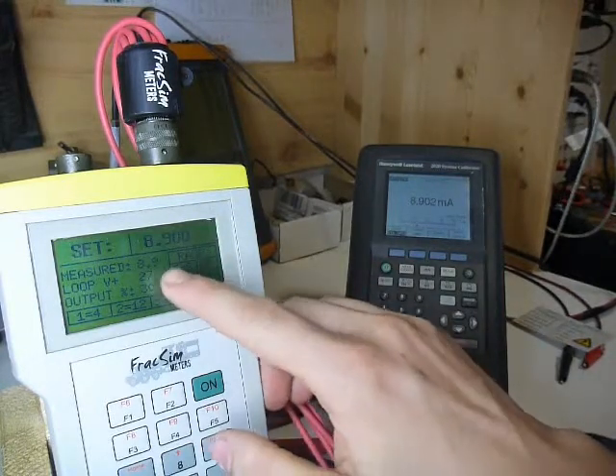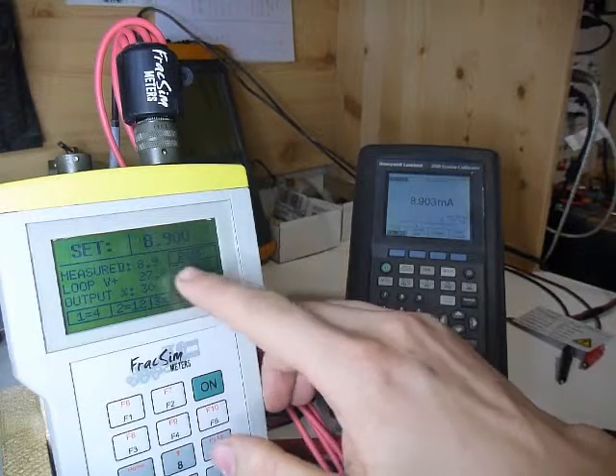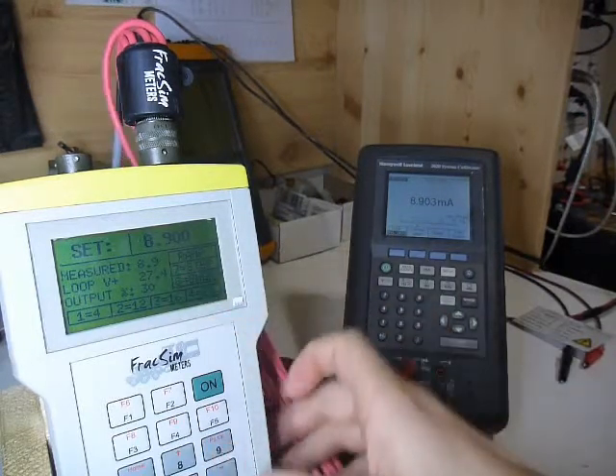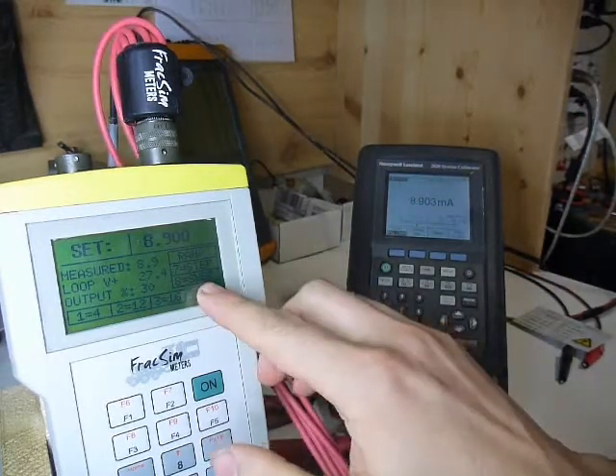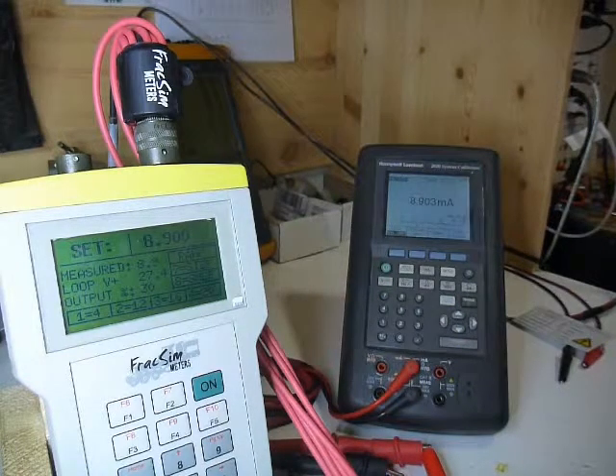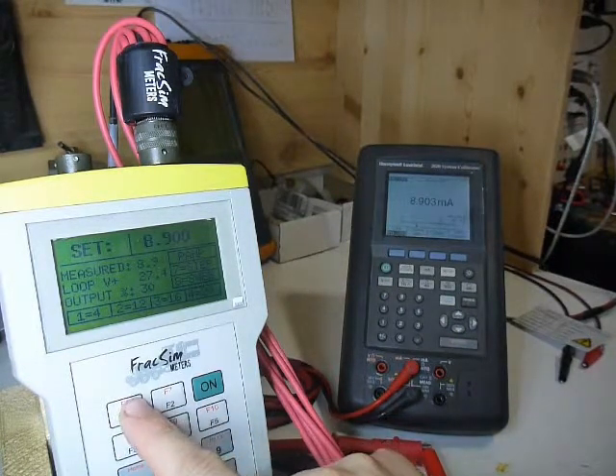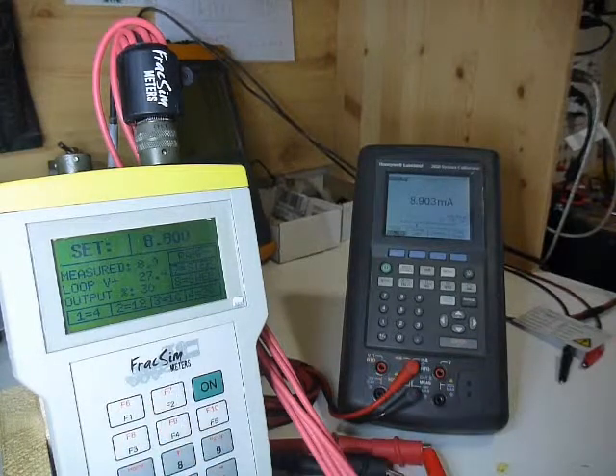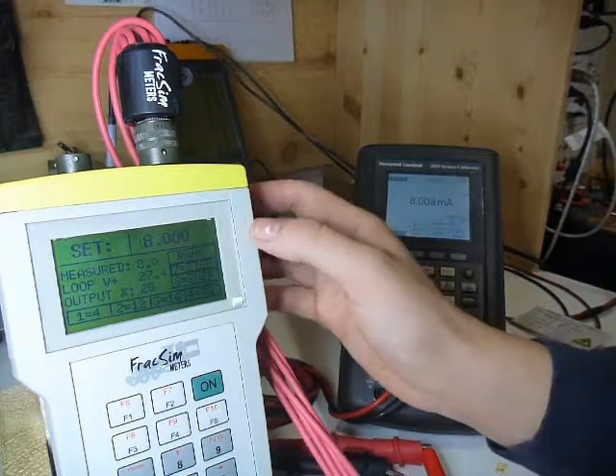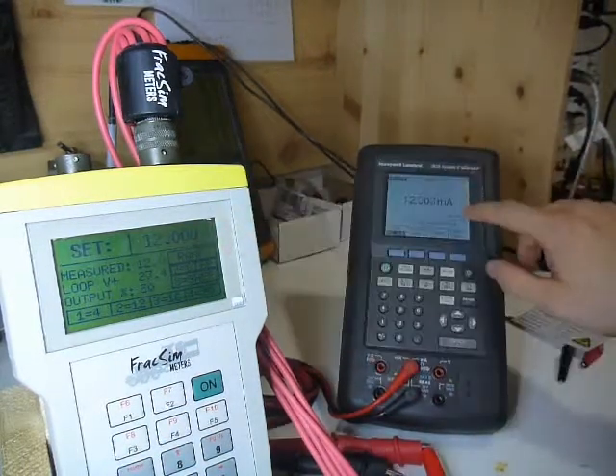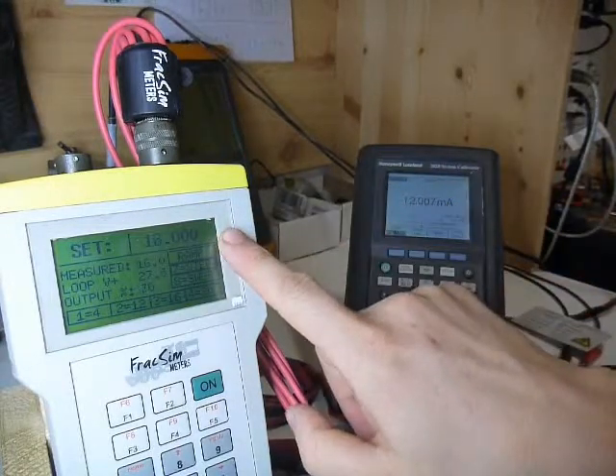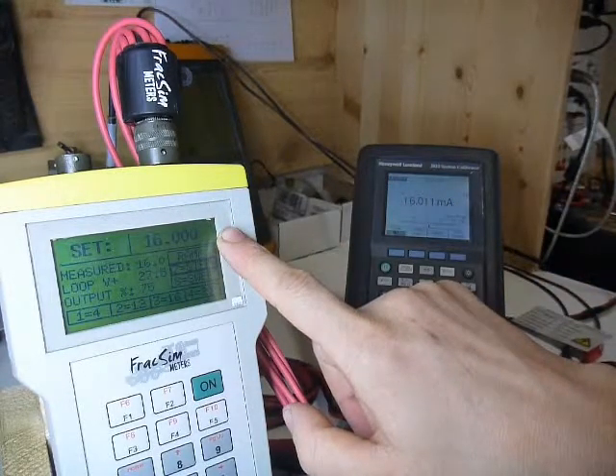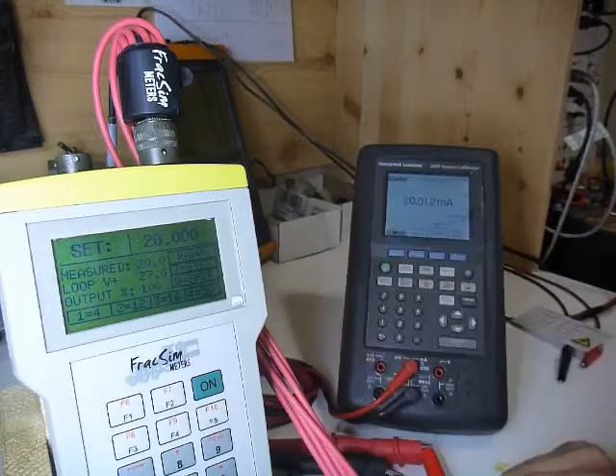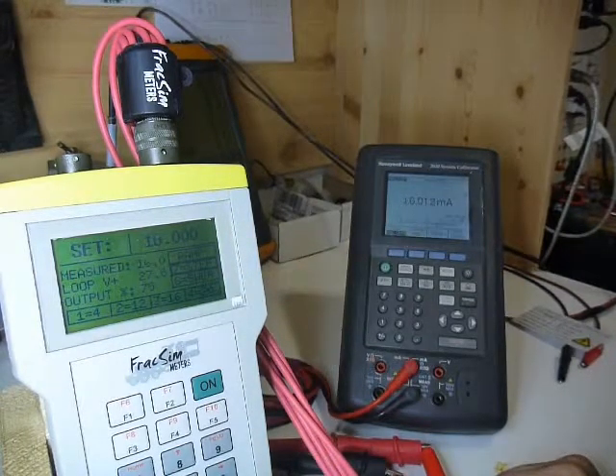And also you see over here there's a box that says ramp, and you'll see 7 is a step and 8 is a sweep. So if you hit shift and then 7, you're going to see that it's going to jump. You could either look there or there, but basically it's going 8, 12, 16, 20. It sits there for a couple seconds and it keeps going back and forth indefinitely.